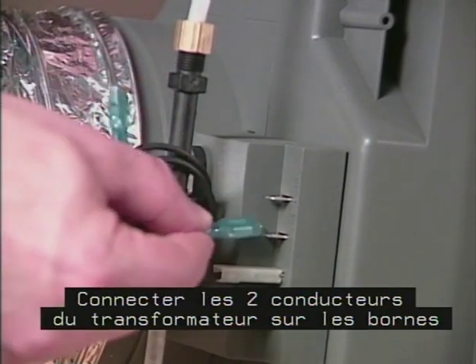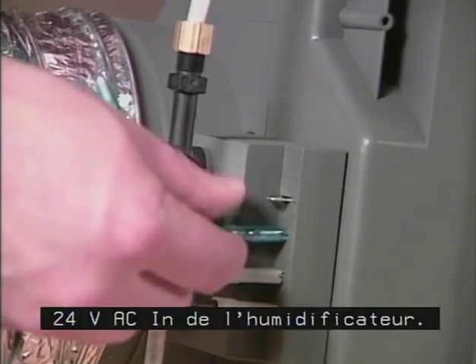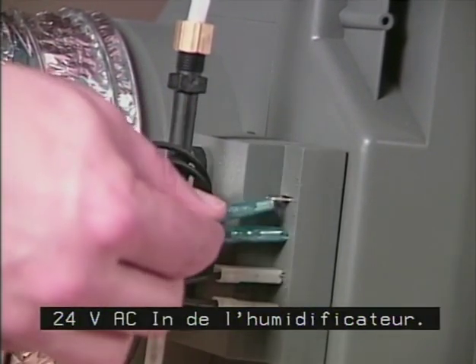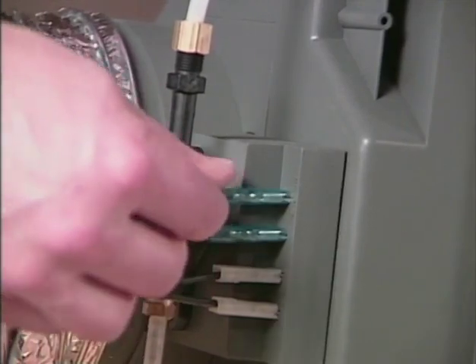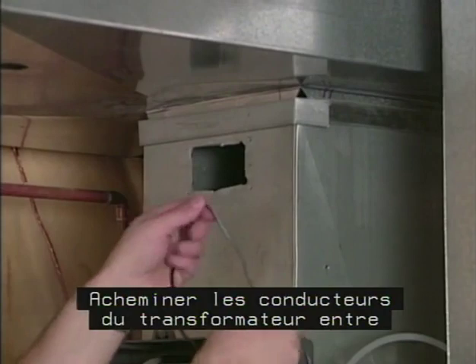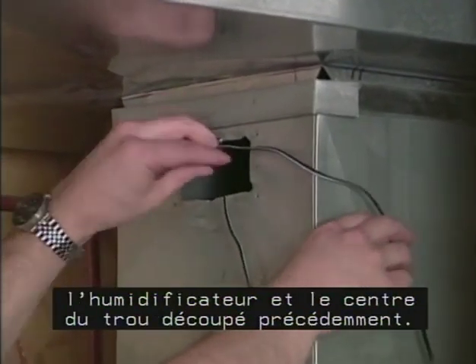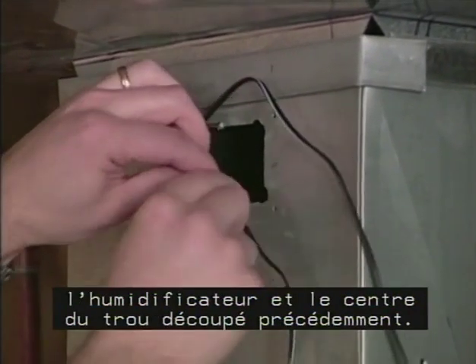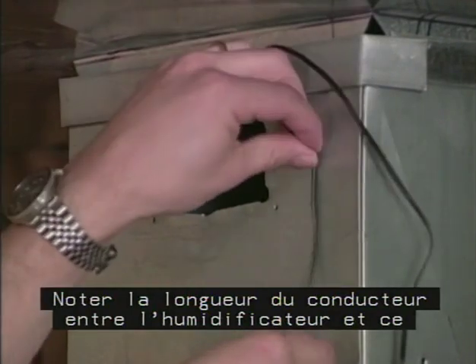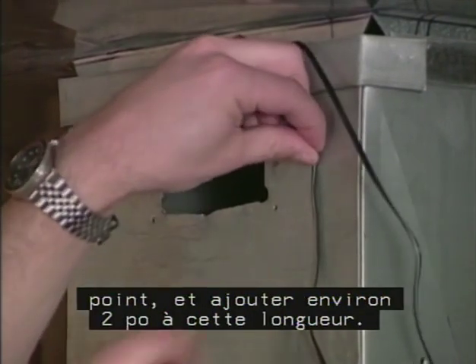Connect the two ends of the transformer lead wires to the humidifier terminals labeled 24 volt AC in. Run the transformer lead wires from the humidifier to the center of the hole created earlier. Note the length of the wire from the humidifier to this point and add approximately 2 more inches to this length.